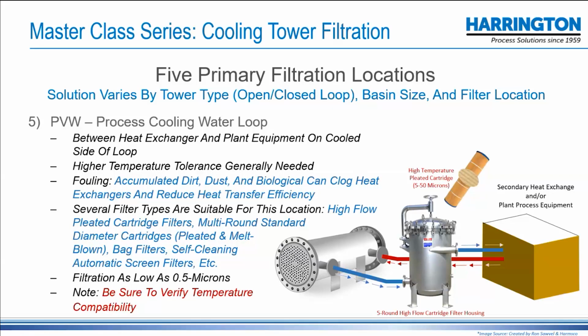But the filter is there to protect your plant equipment and also to keep the plant side of the heat exchanger clean. If we have the right filter on the cooling tower, we're keeping the cooling tower side clean, but that heat exchanger has two sides.